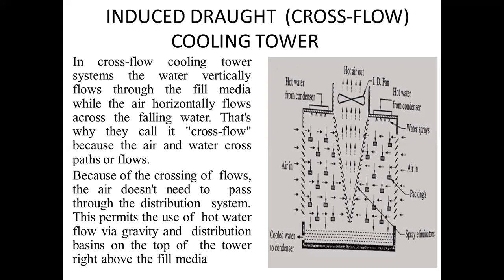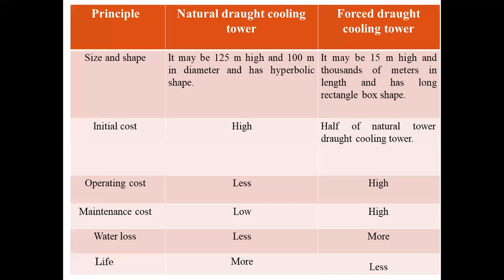Because of the crossing of flow, the air does not need to pass through the distribution system. This permits the use of hot water flow via gravity and distribution basins on the top of the tower right above the fill media. Right. You can say comparison between natural draft and forced draft cooling tower.